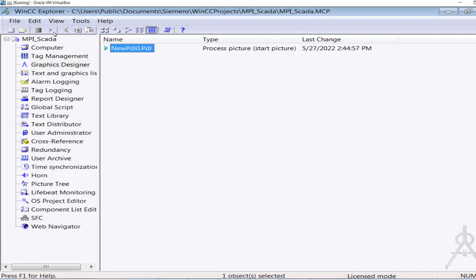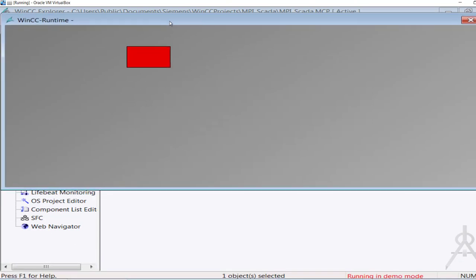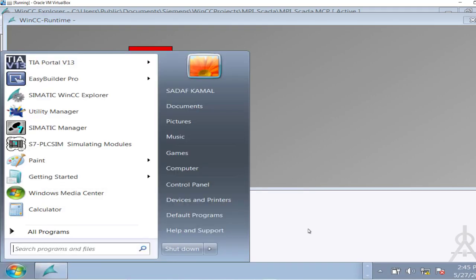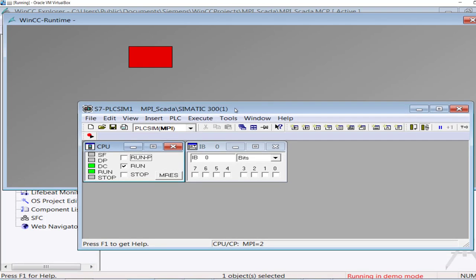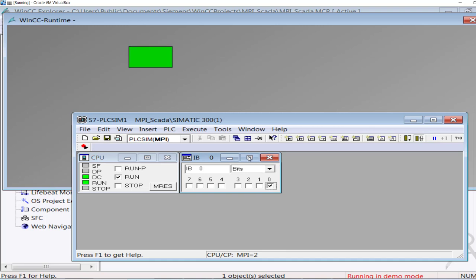Now go to runtime. The color of the rectangle follows my setting: if the first digital input of the digital input card is low, the rectangle is lit red. It will be lit green if the status of the digital tag is high. Right-clicking on the simulator, I will set the first digital input of the first digital input card to high — and here it has been lit green.